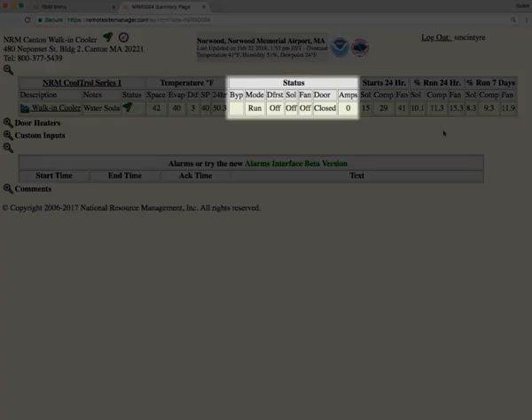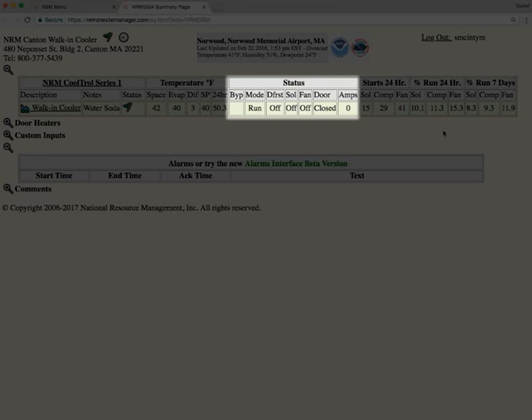This status section is the status of the controller. Run mode means that our system is in control. You can put our system into bypass by clicking on the run mode and put our system into bypass by clicking OK. Bypass is the scenario where it takes all of our control aspect out of the loop and puts the old existing system back into control.